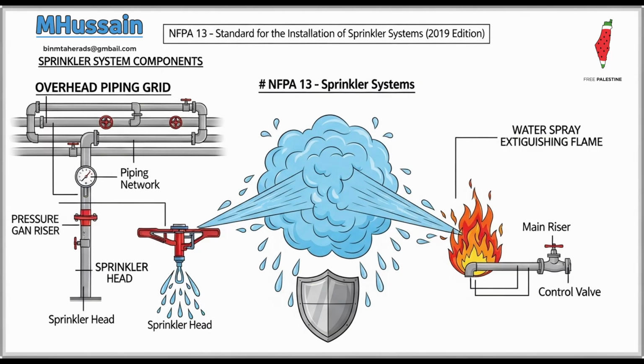And that brings us perfectly to our final provocative thought for you, the listener, to consider. It involves a key and sometimes confusing interaction between fire codes and electrical codes. NFPA 13 explicitly prohibits using the sprinkler system piping as a primary grounding electrode for the building's electrical system. However, NFPA 70, which is the National Electrical Code, requires that all metallic piping systems, including sprinkler pipes, be bonded to the electrical grounding system. This is done to disperse stray electrical currents and equalize electrical potential.